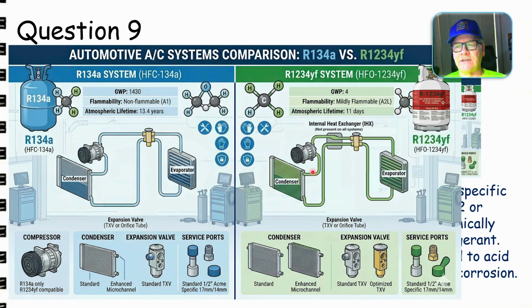Like I say, if you see any errors in here, just let me know where I went wrong. You'll notice this says a heat exchanger that actually had both the suction and liquid lines go through. The suction line, on the way to the compressor, absorbs some heat from the liquid line so that it cools it off. Of course your subcooler has already done that, but they wanted to run this through, and they did that. They came up with that because R1234 does not work quite as well as R134A.